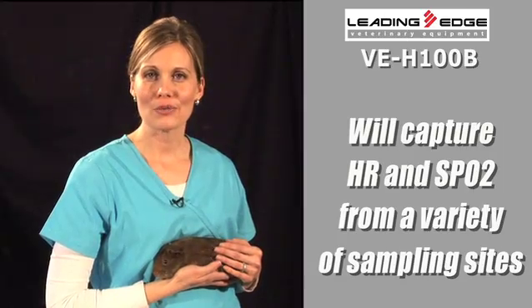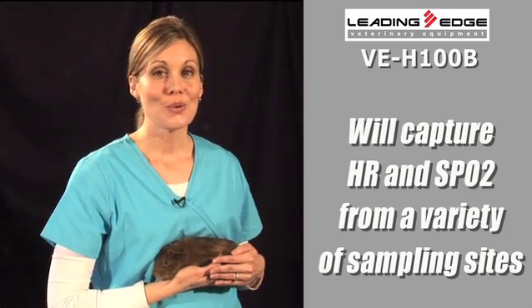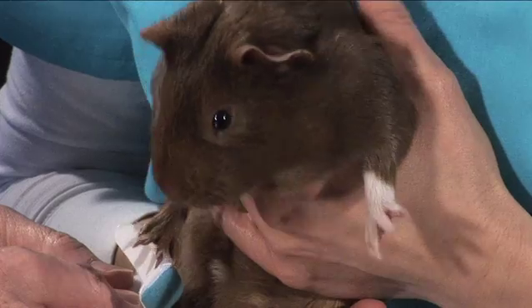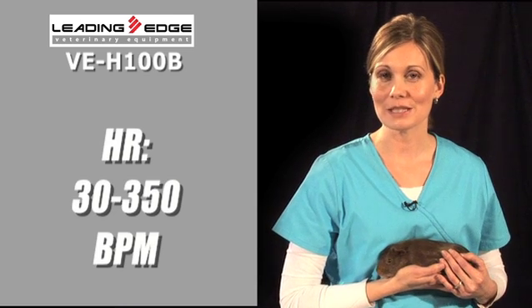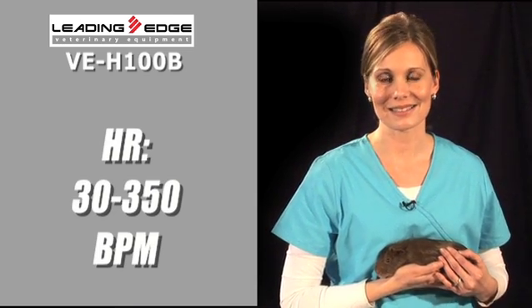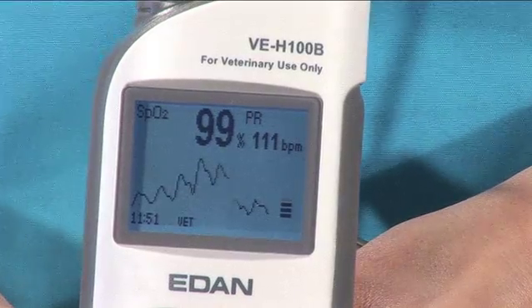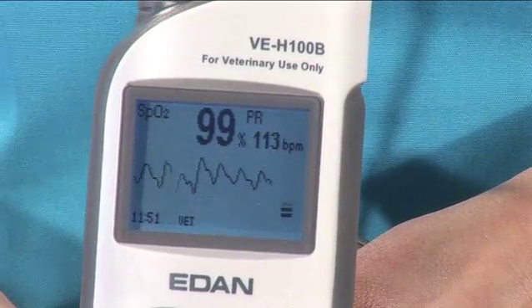At least one of these will capture heart rate and SpO2 from a variety of patient sampling sites with almost any animal you see, even Coco the guinea pig. The VE-H100B's heart rate range of 30 to 350 beats per minute accommodates all species from equine to exotics.